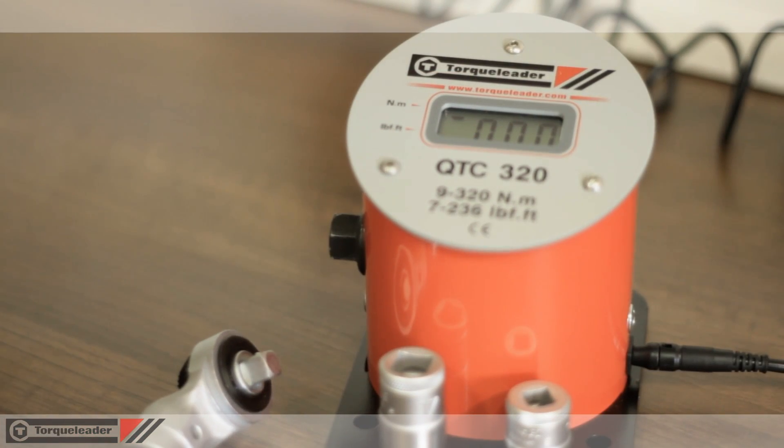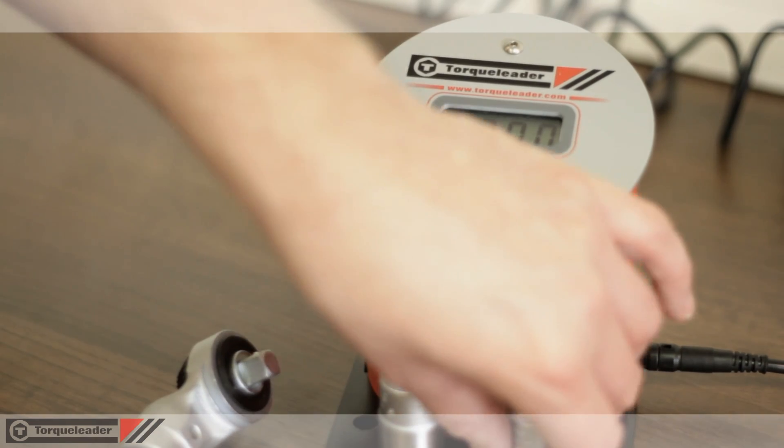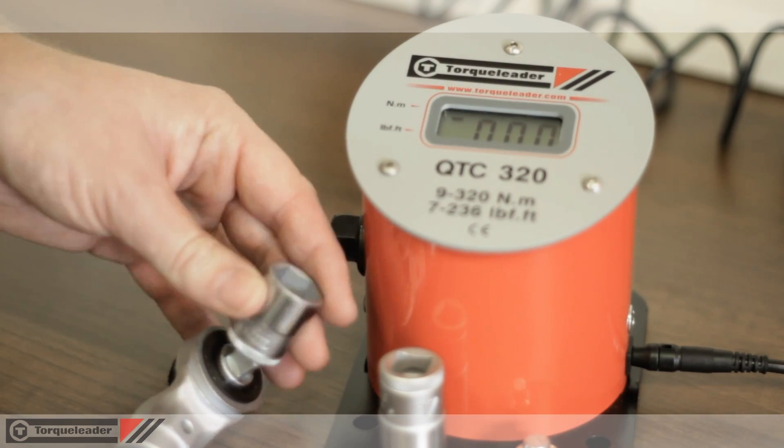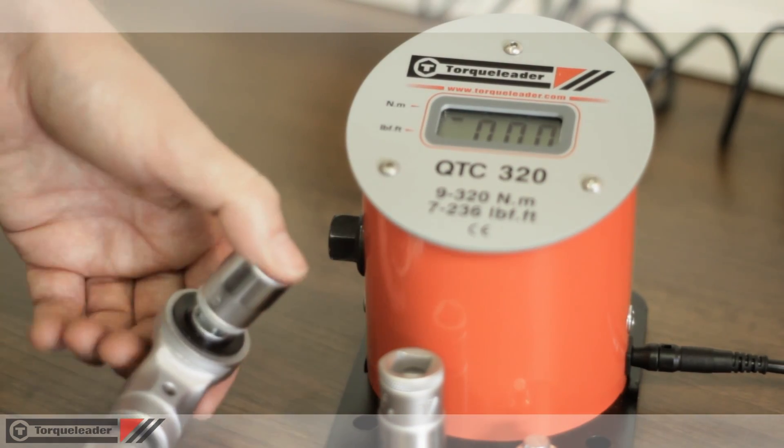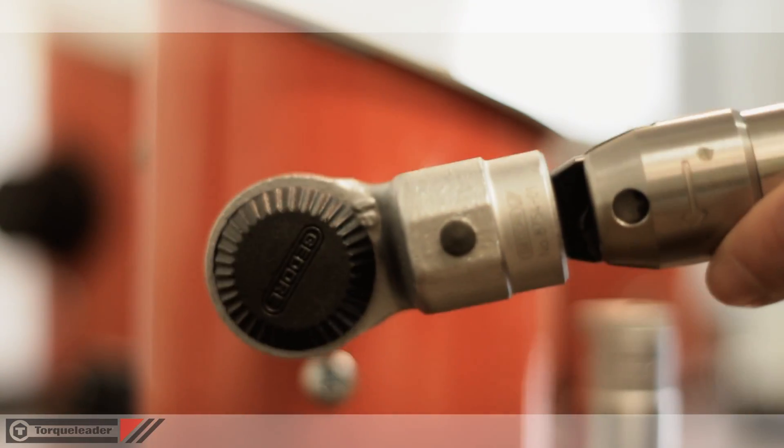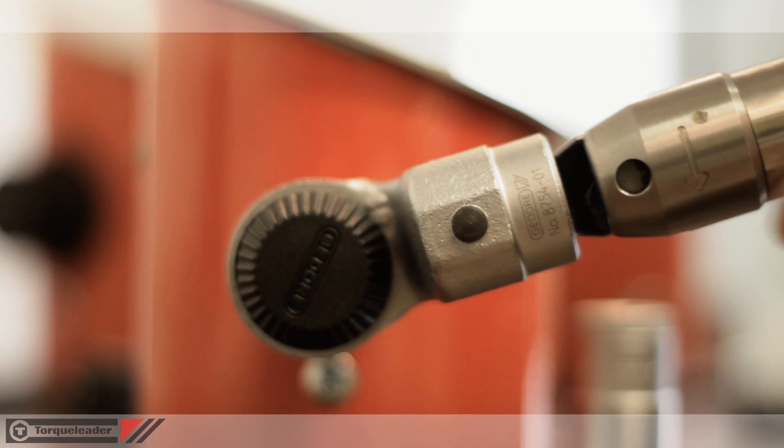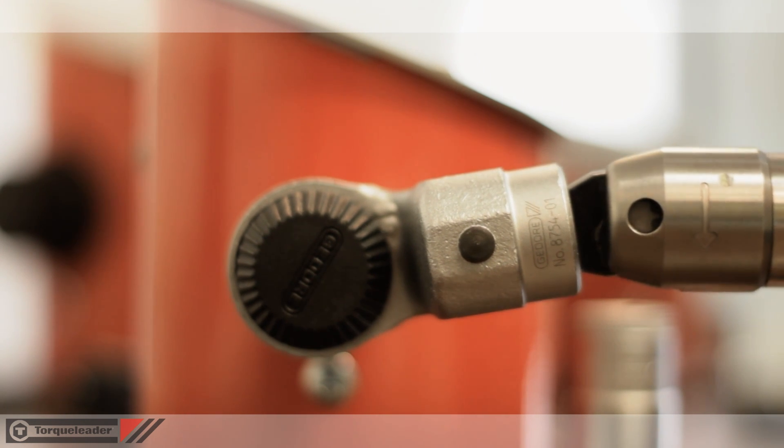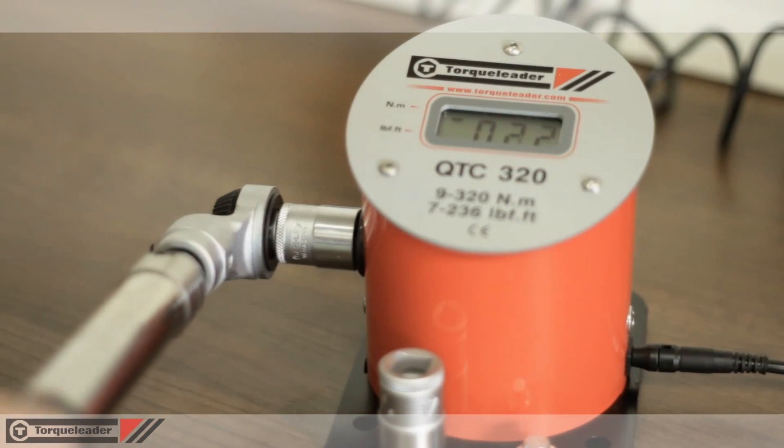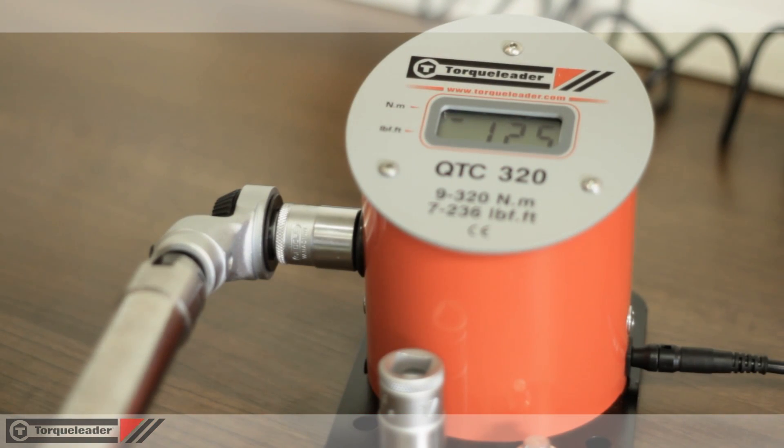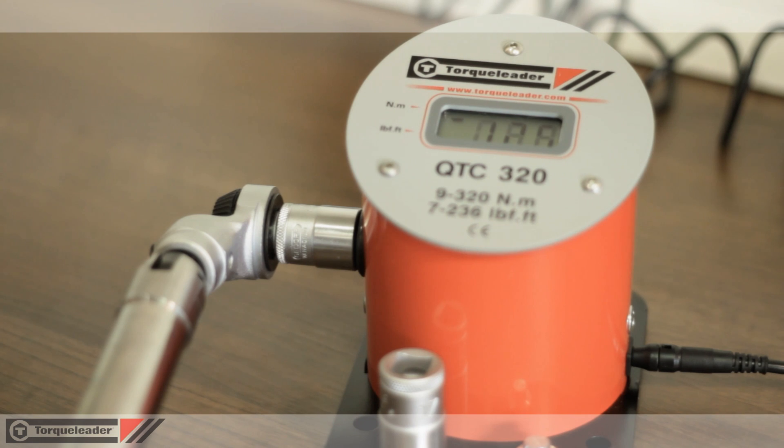The QTC is extremely easy to use. Simply connect the drive adaptor to the torque wrench and apply torque. The peak torque value appears on screen.